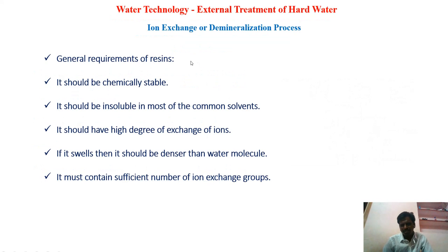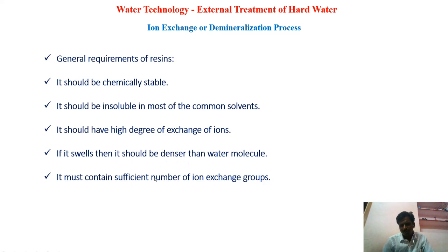The basic requirements of resins are: they should be chemically stable and should not react with water — that means insoluble in water and in most common solvents. They should have a high degree of ion exchange, meaning exchange of ions between water and resin should be very quick. The resin should be denser than water so that it stays immersed rather than floating. It should also have a sufficient number of functional groups — if the number is too low, most ions will be left untreated.